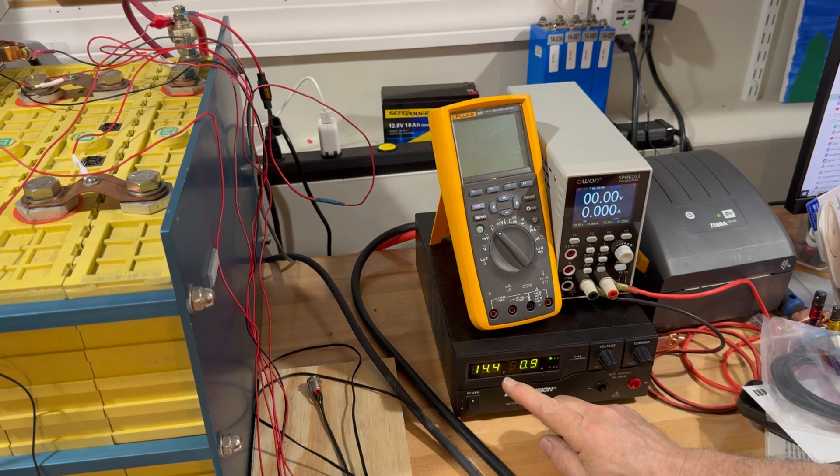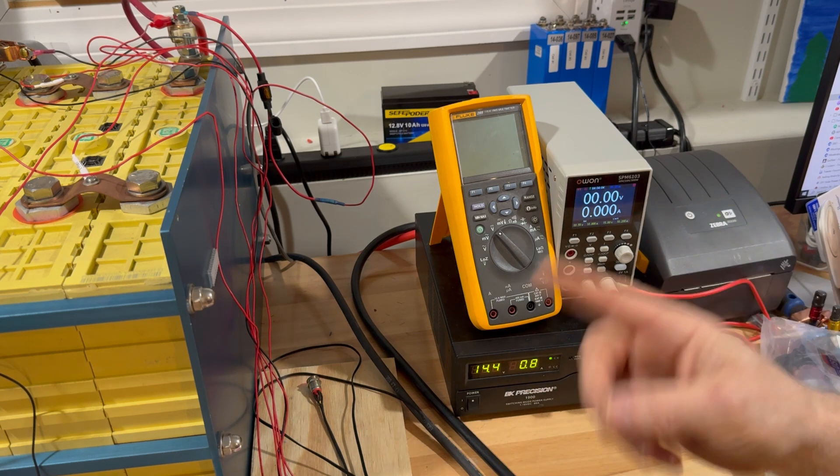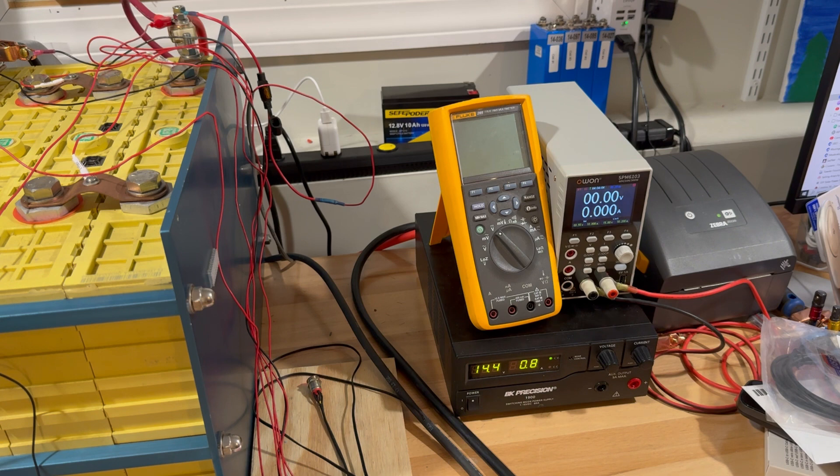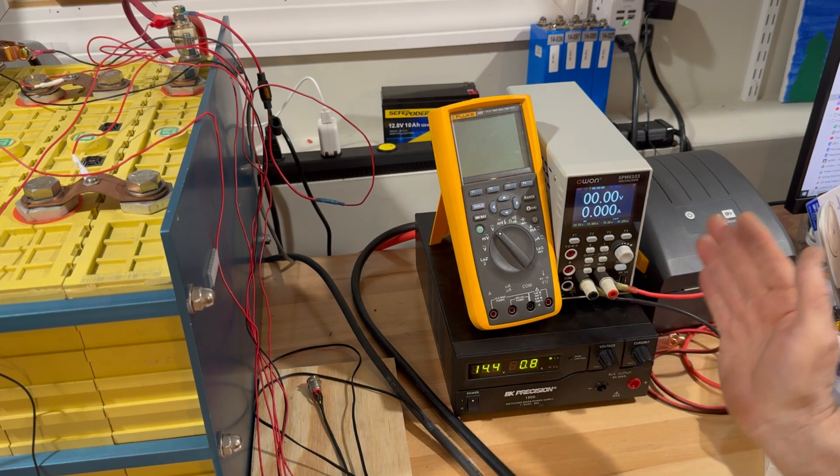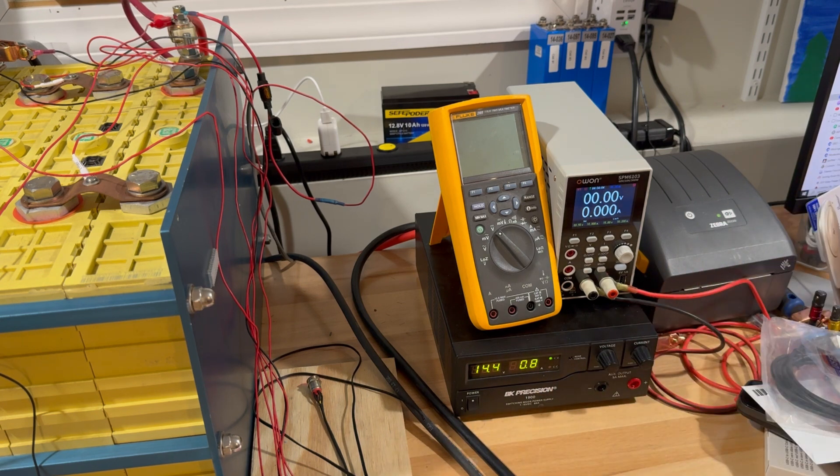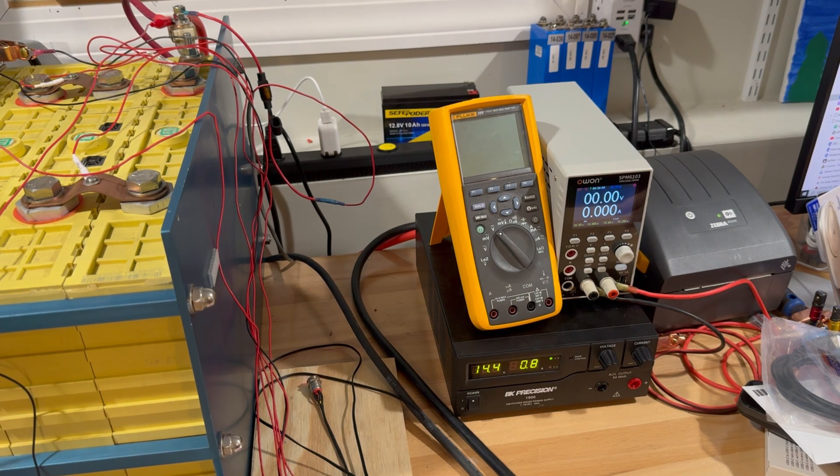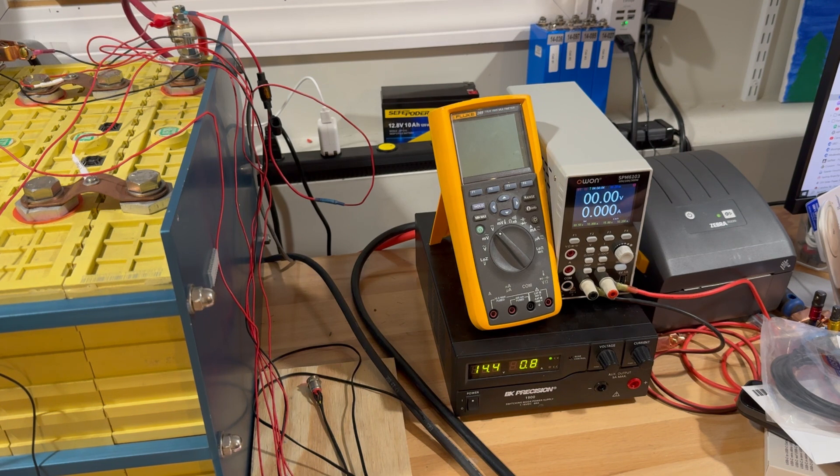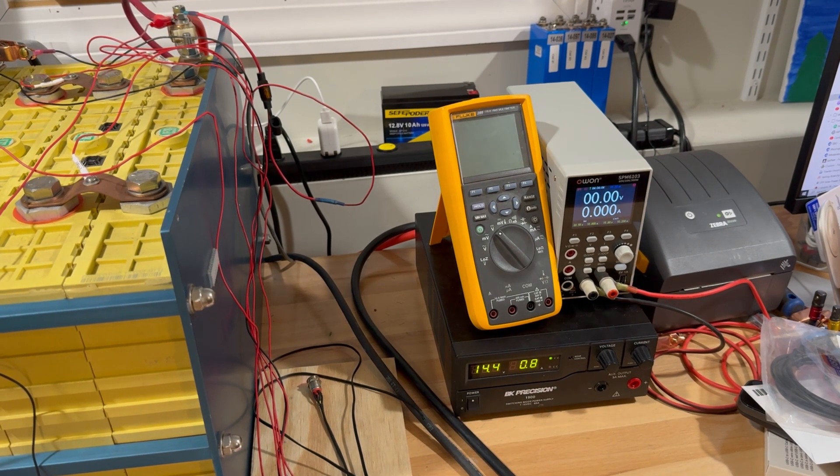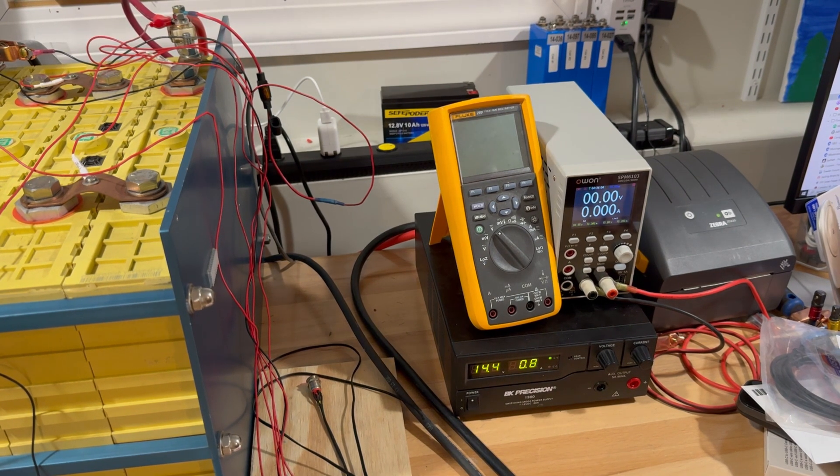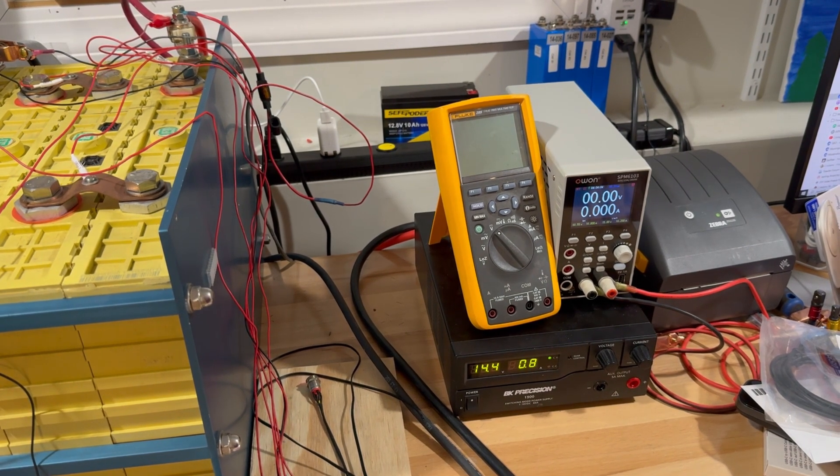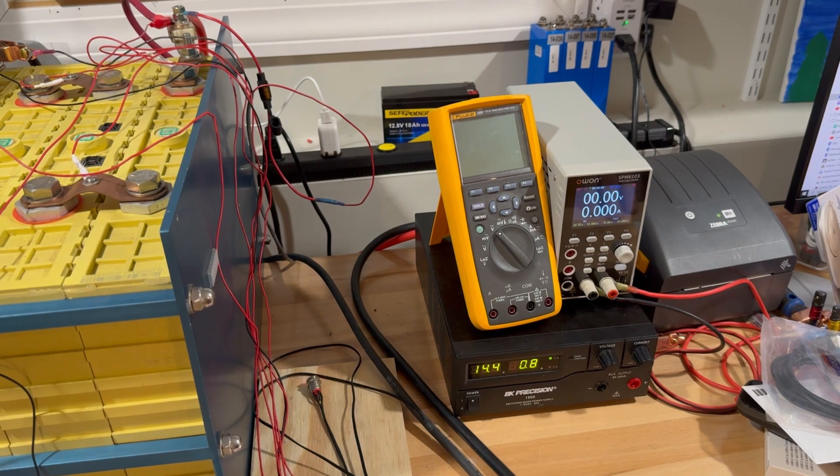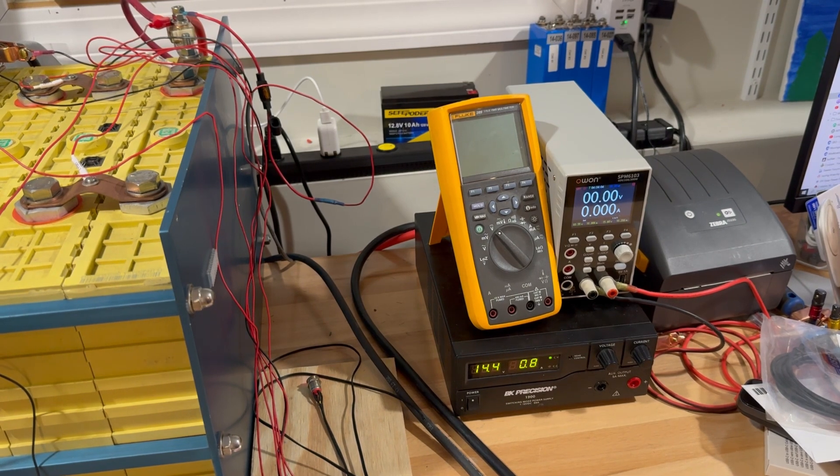If I were to put a big load on this battery bank right now you'd see this go right back to 60 amps again. Then once you took the load off the same thing would happen again. I hope this helps and maybe it puts a little into the myths about constant voltage and constant current and how much energy is stored above 13.8 volts or 3.45 volts per cell. Take care guys.